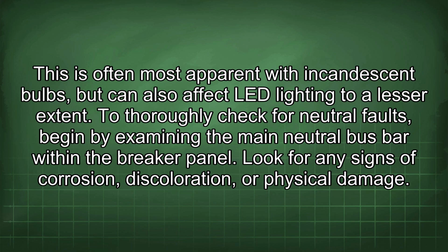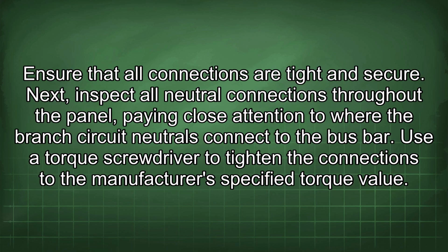To thoroughly check for neutral faults, begin by examining the main neutral bus bar within the breaker panel. Look for any signs of corrosion, discoloration, or physical damage. Ensure that all connections are tight and secure. Next, inspect all neutral connections throughout the panel, paying close attention to where the branch circuit neutrals connect to the bus bar. Use a torque screwdriver to tighten the connections to the manufacturer's specified torque value.